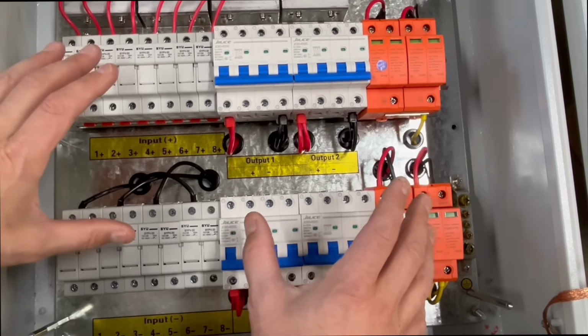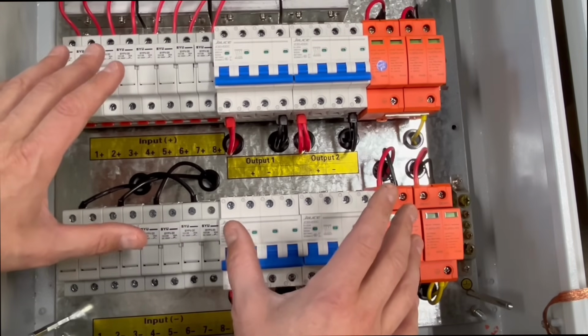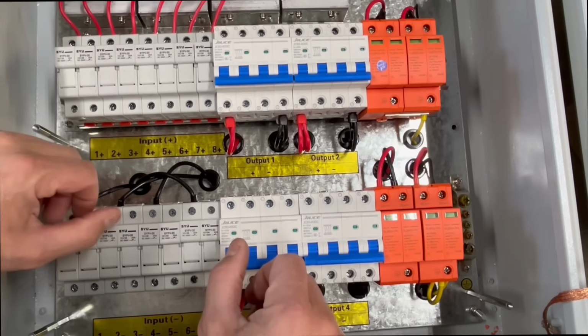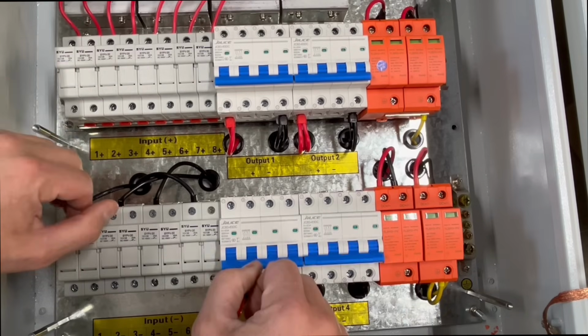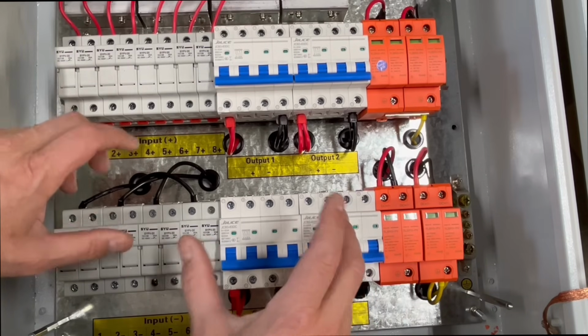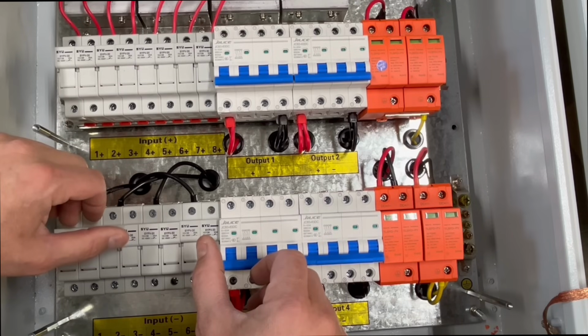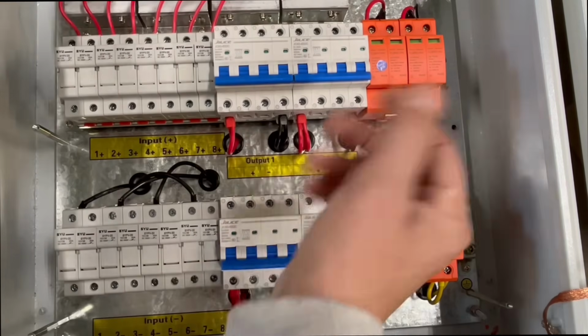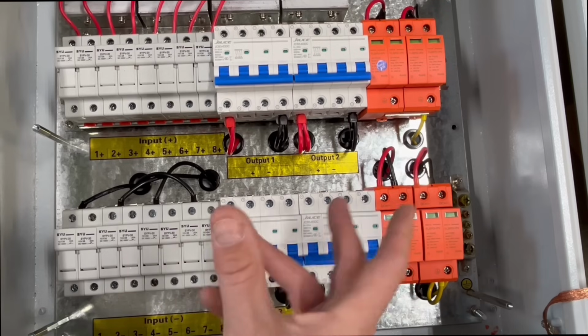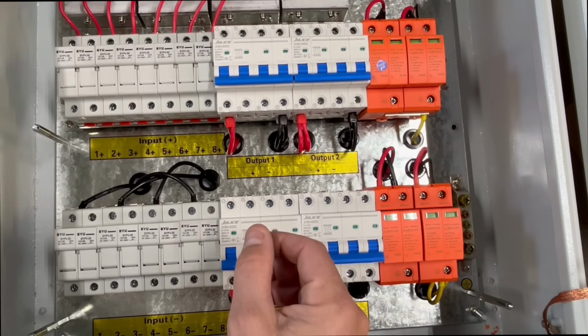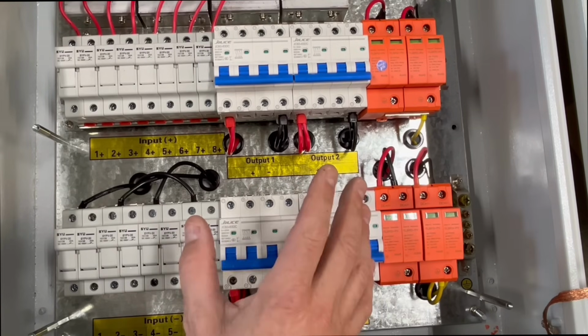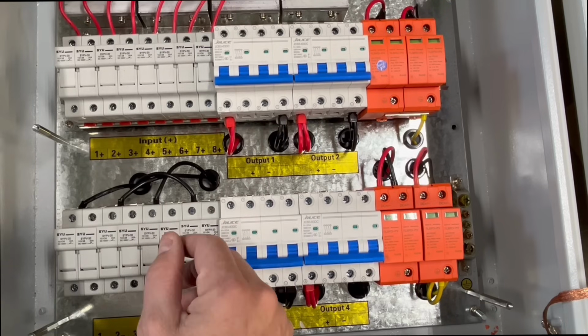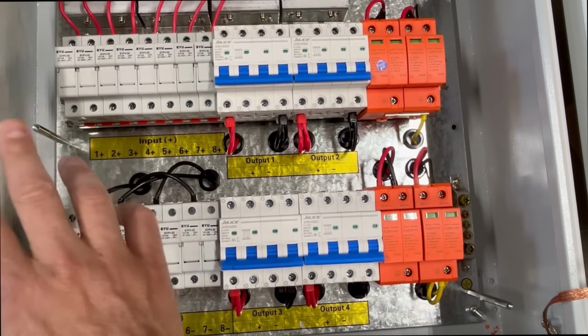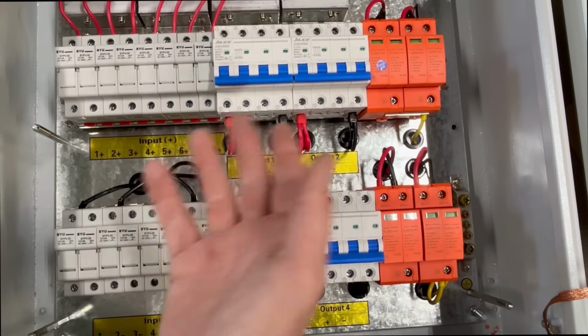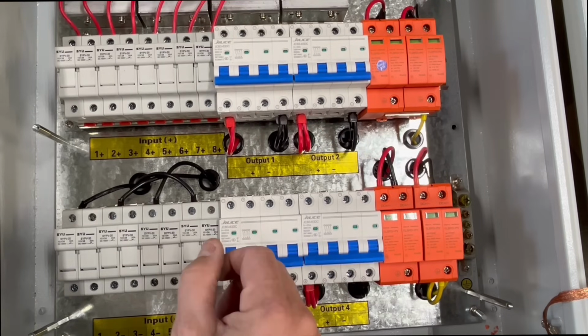All right, so this 8-4 combiner box looks pretty intimidating at first if you haven't looked inside of a combiner box before, but it's actually not that bad. If you were to break it down to a 4-2 combiner box, which I discussed in my last video, then it would just be this right here. So you just have four different inputs, two different outputs. For some of you, it may be easier to think of it as a parallel box instead of a combiner box, because really you're just paralleling strings. In this case, you're going to want two strings tied together and turned into one as it comes back out.